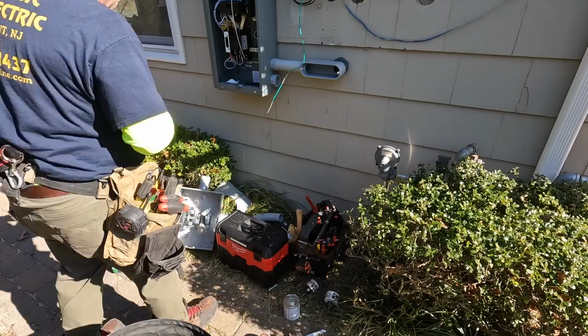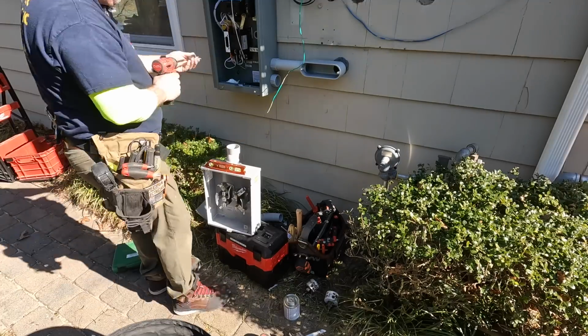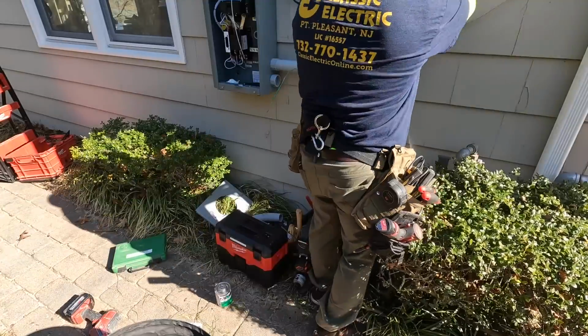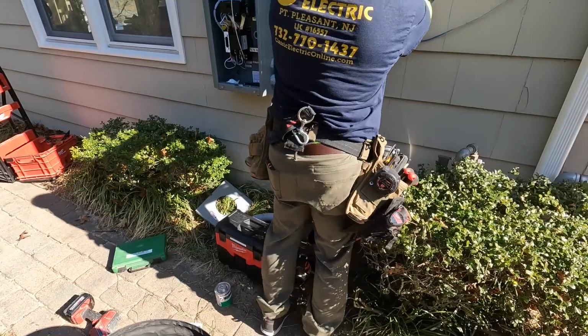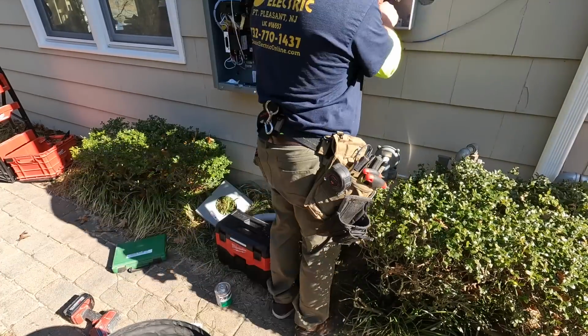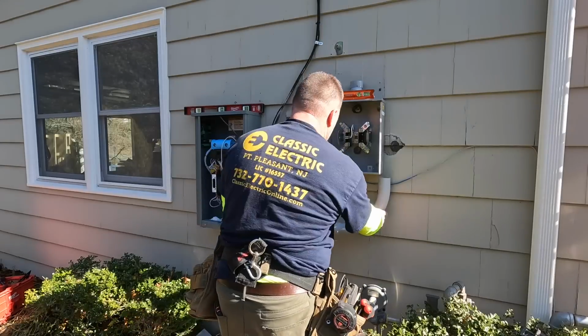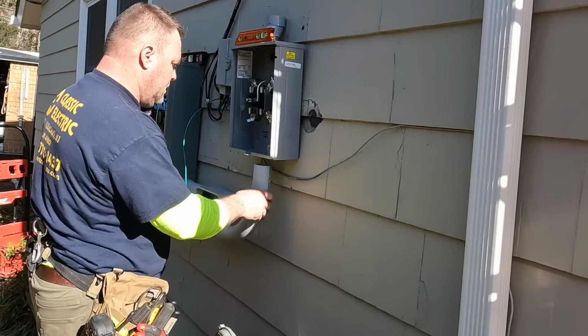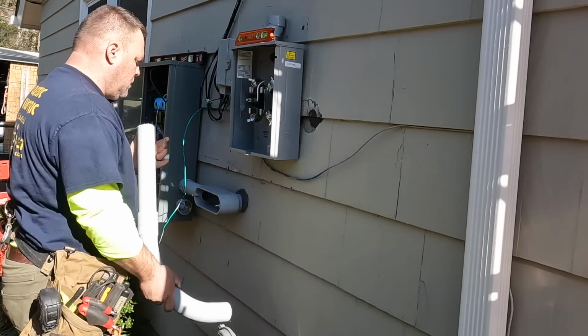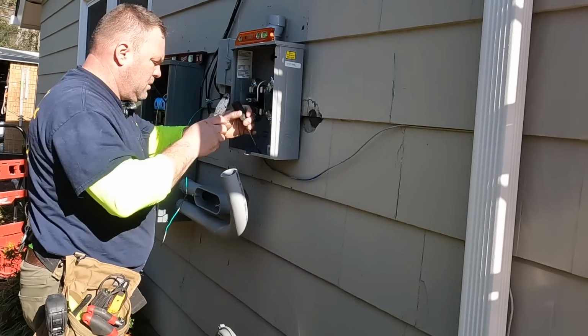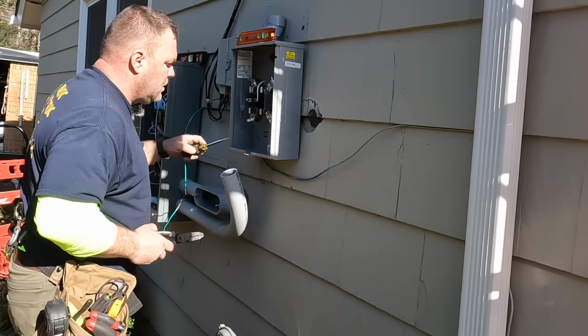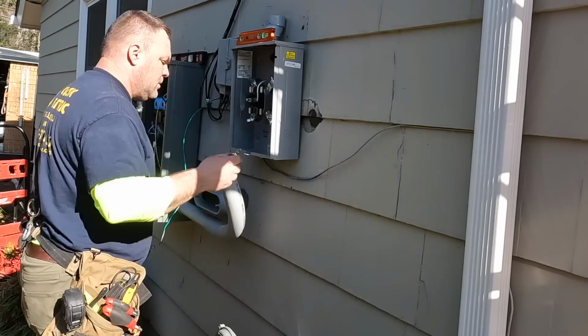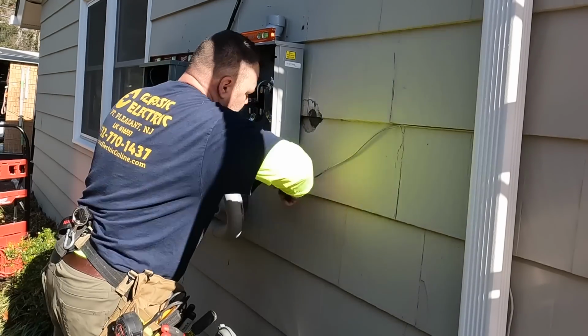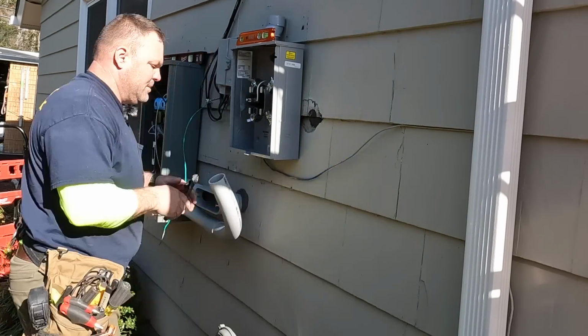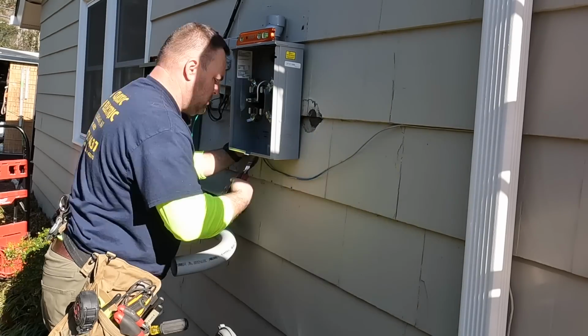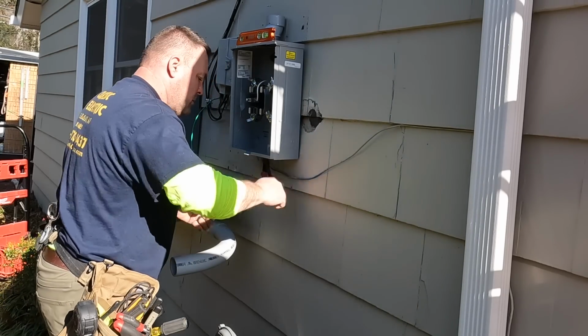So what am I doing here? Still attaching screws, I believe. I'm getting ready to mount the 200 amp meter, and it's not a meter-main combination because the transfer switch is an automatic transfer switch, 200 amp, and it's a service-rated transfer switch. So that's going to act as not only the transfer switch for the generator and utility transfer, but also the emergency disconnect required by NEC Article 230.85.